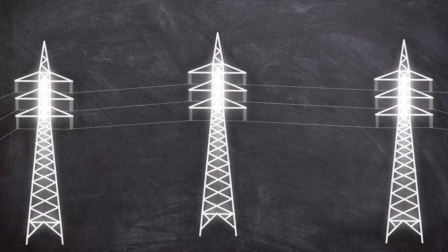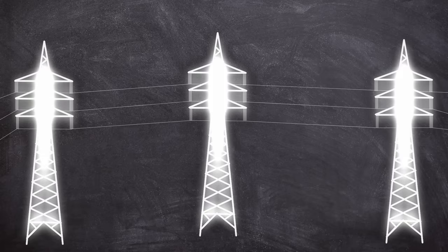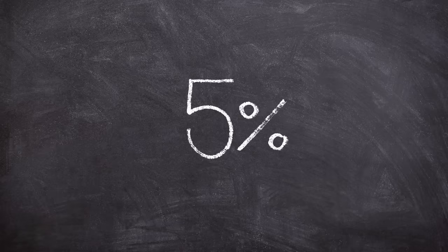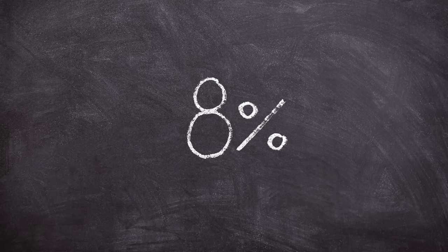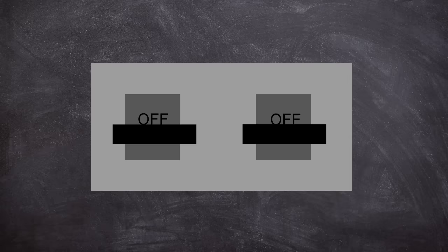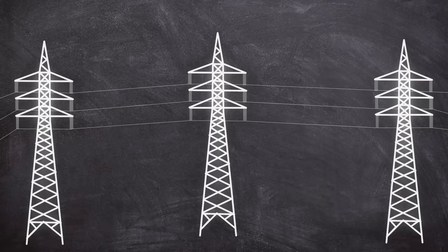It was ever becoming apparent that Con Edison needed to load shed. Initially, a 5% power reduction followed by an 8% reduction at 9:19 p.m. took place. Another substation tripped due to thermal overload. But by 24 minutes past 9, this was not working, and the system was still very much overloaded.